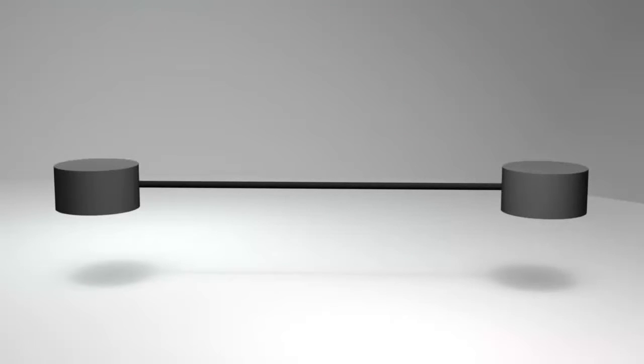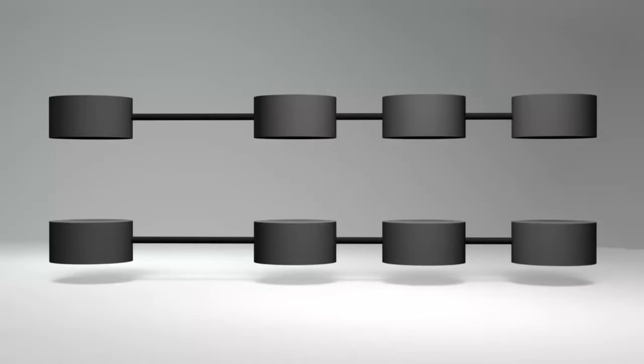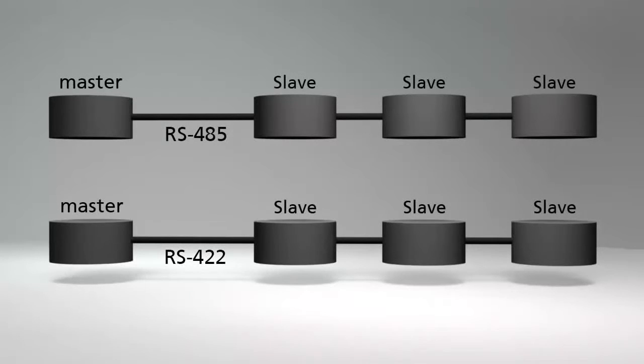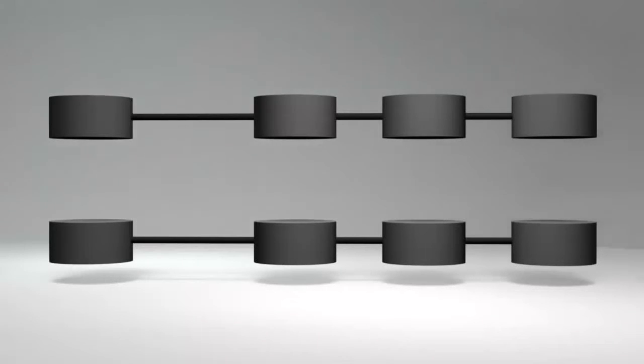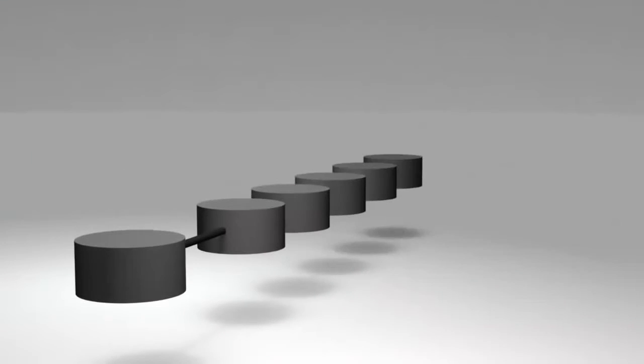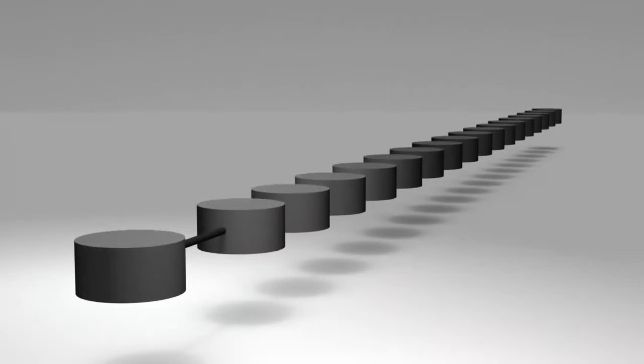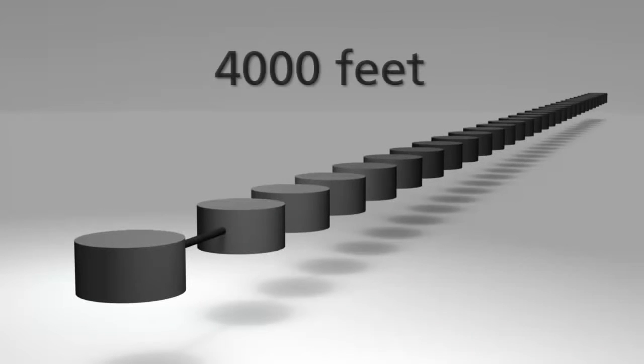To connect more than two devices on the same line and/or have a distance greater than 50 feet, you should use RS-485 or RS-422. For a master communicating with multiple slave devices, RS-485 is by far the most popular method. This standard can support up to 32 nodes over a range of up to 4,000 feet, roughly 1,200 meters, without a repeater.